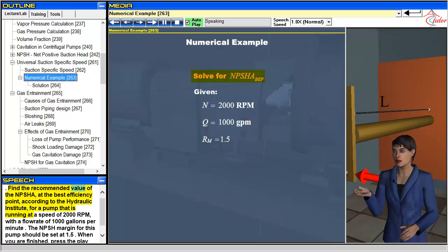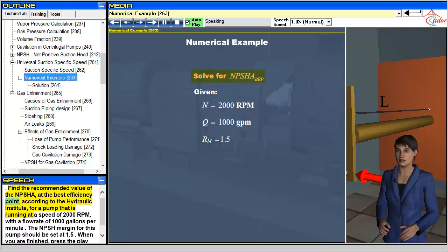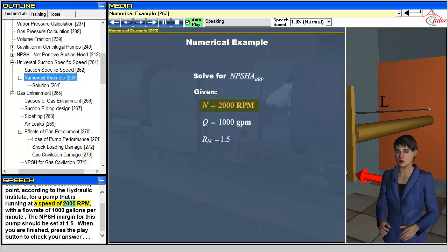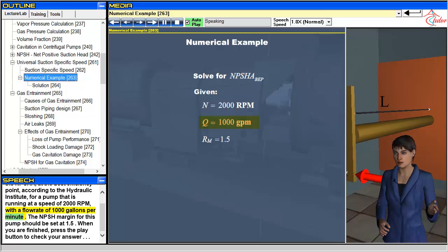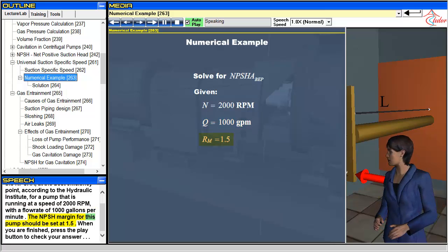Find the recommended value of the NPSHA at the best efficiency point, according to the Hydraulic Institute, for a pump that is running at a speed of 2,000 rpm with a flow rate of 1,000 gallons per minute. The NPSH margin for this pump should be set at 1.5. When you are finished, press the play button to check your answer.